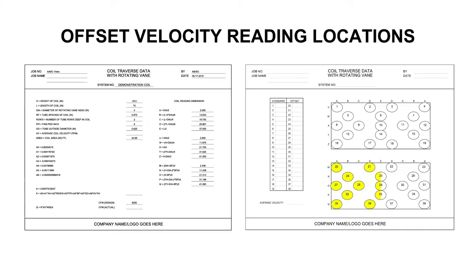Next, measure and mark the offset velocity reading locations 20 through 38, by referencing the coil reading dimensions A through E and M through Q. The same method is used to mark the intersections of the offset velocity reading locations as was used to mark the standard velocity reading locations. The offset velocity reading location markings are a different color to differentiate between the standard and offset velocity reading locations.